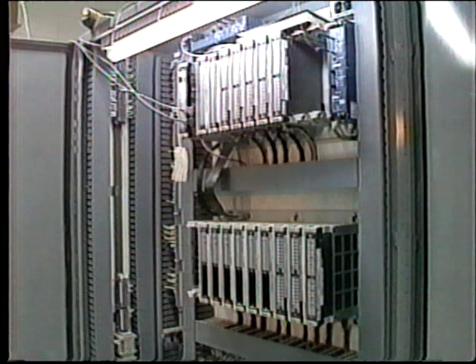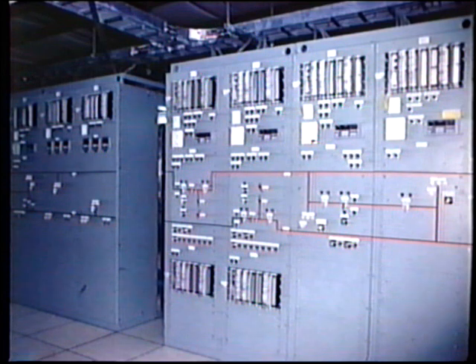In discussing inputs and outputs to the PLC, we have seen that there are a variety of arrangements available according to the specific application. Even though PLCs are interchangeable to a certain extent, we must certainly be aware of the types of input signals available and output signals required by the installation and specify accordingly. In some PLCs, plug-in input and output modules are used. This facility enables us to configure the interface to suit each specific terminal requirement.